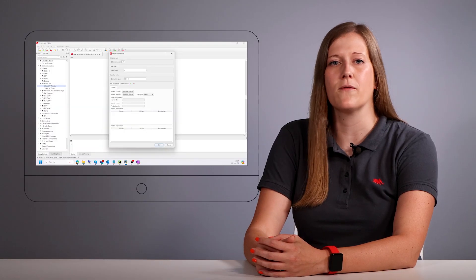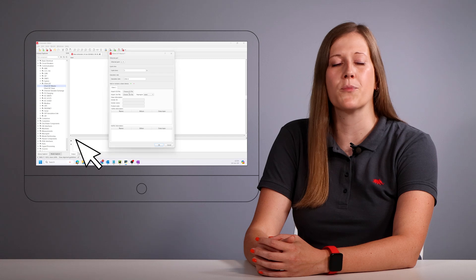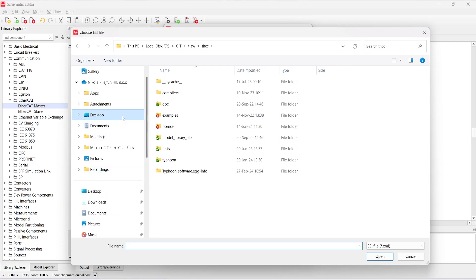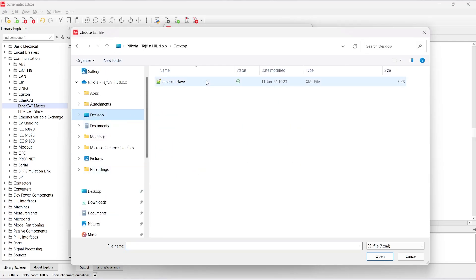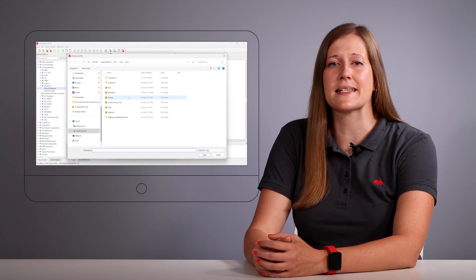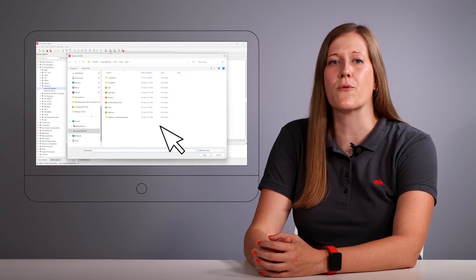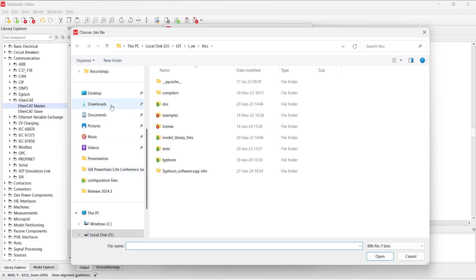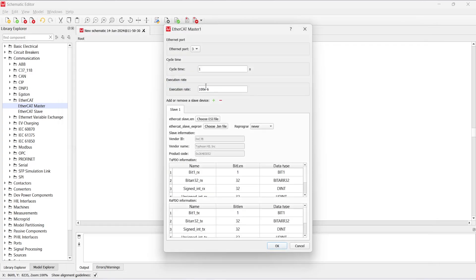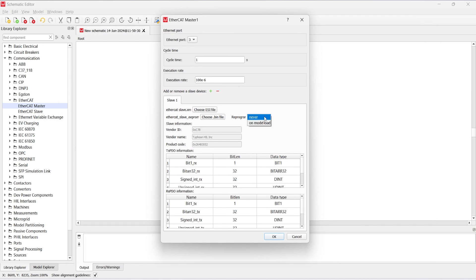To define the slave device, we need to choose and import an ESI file from our computer. Once loaded, we can observe information about the slave device, such as vendor information and the contents of its process data objects. Finally, we can also choose to reprogram the slave device directly from the master on its model load. We do this by importing its binary file.